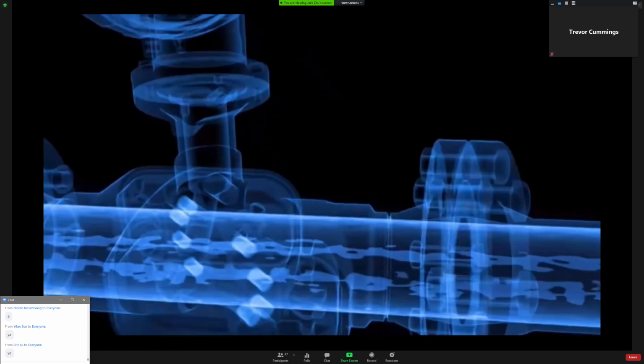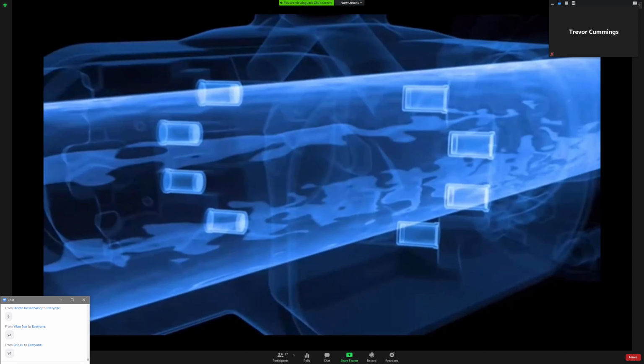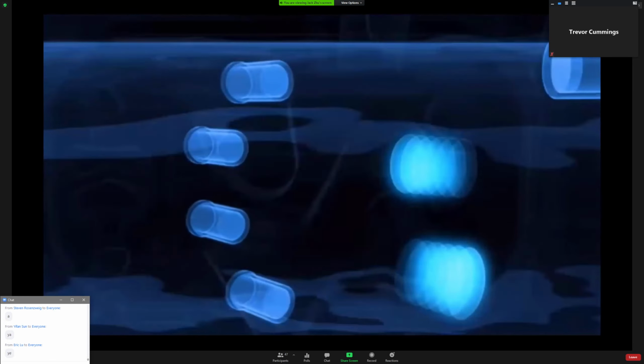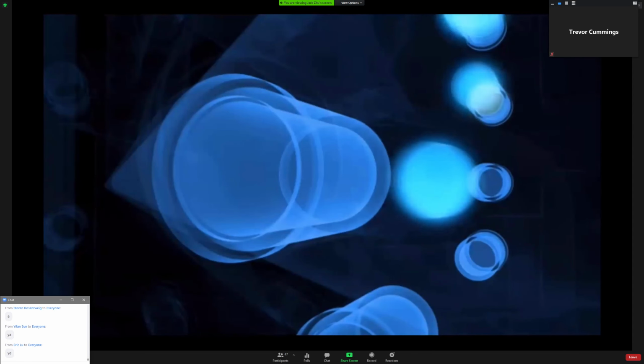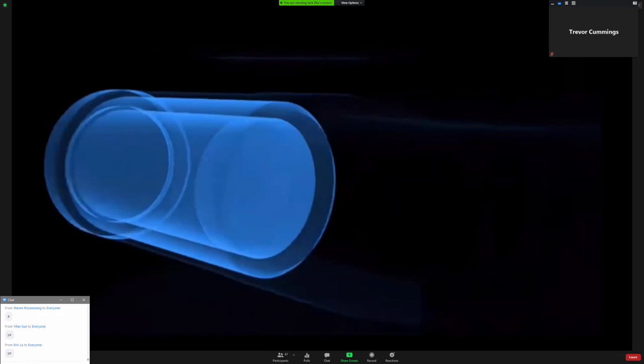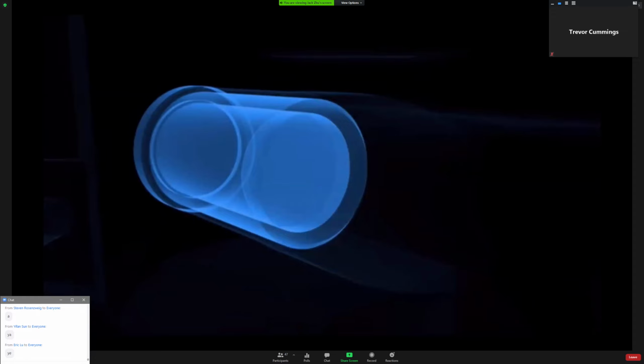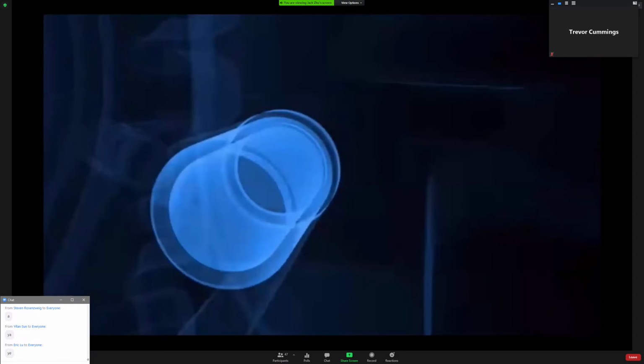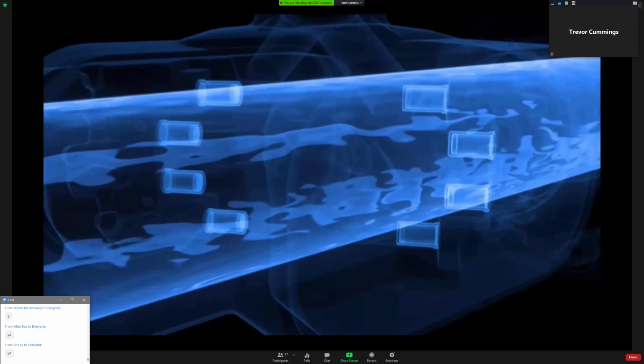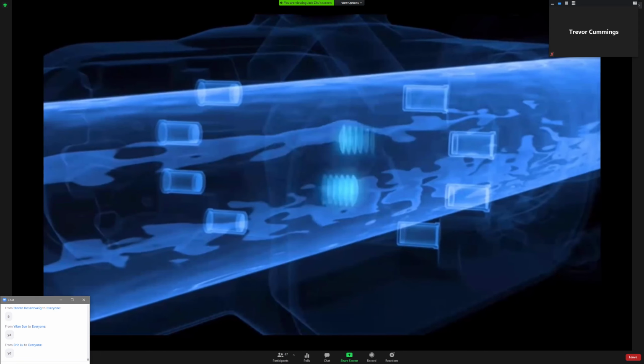Inside the ultrasonic Flowmeter, pairs of sensors are fitted across from each other in the measuring tube. Each sensor can alternately transmit and receive an ultrasonic signal. Simultaneously, the transit times of these signals are measured. The ultrasonic signals are generated with piezoelectric crystals applying a voltage. Conversely, a piezoelectric crystal creates a voltage when an ultrasonic signal impacts the sensor. By increasing the number of sensor pairs, it's possible to accurately detect and mathematically compensate for flow profile distortions over the entire pipe cross-section. When there is no flow, the signal transit times are the same, upstream and downstream.